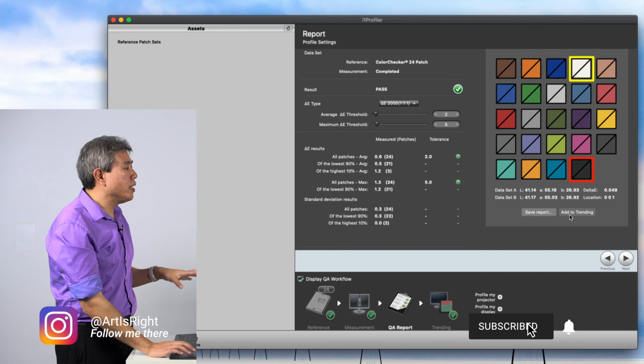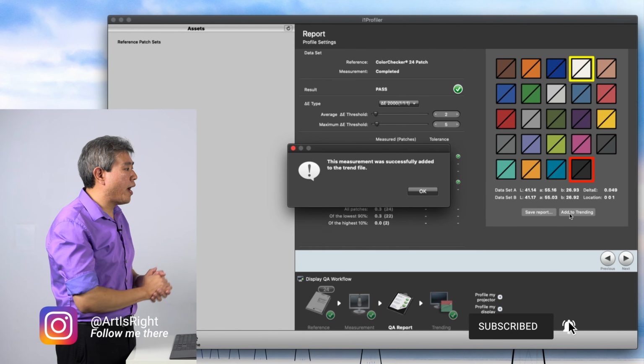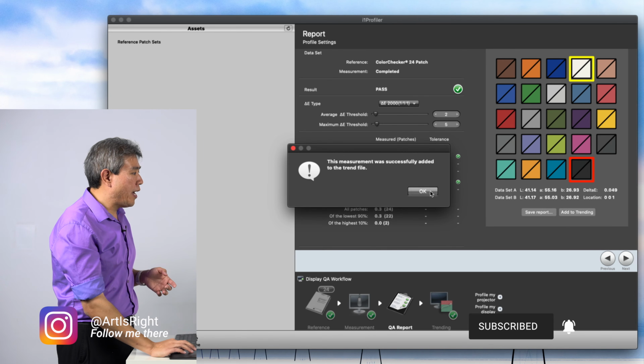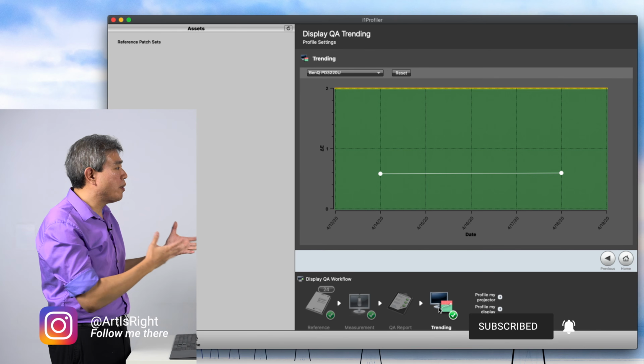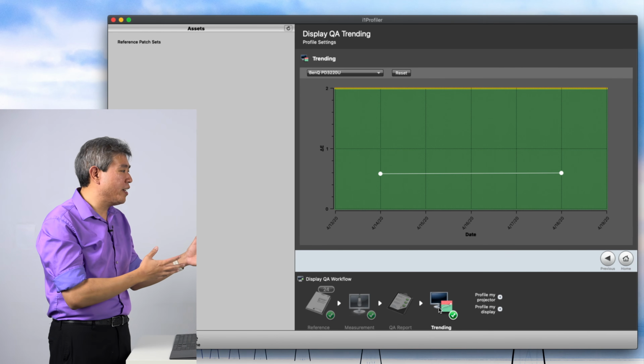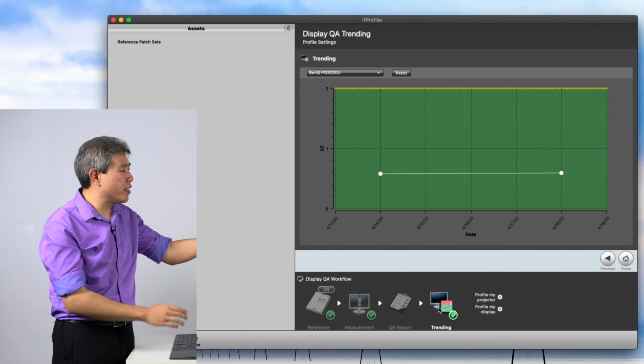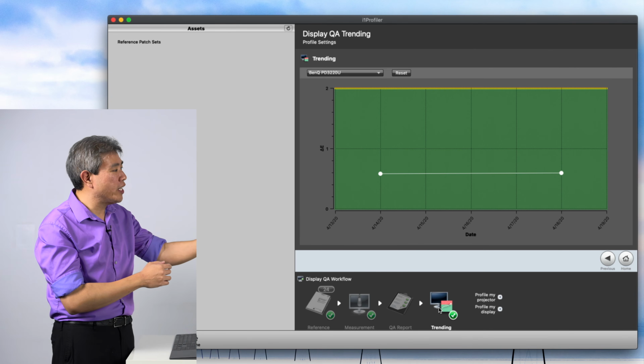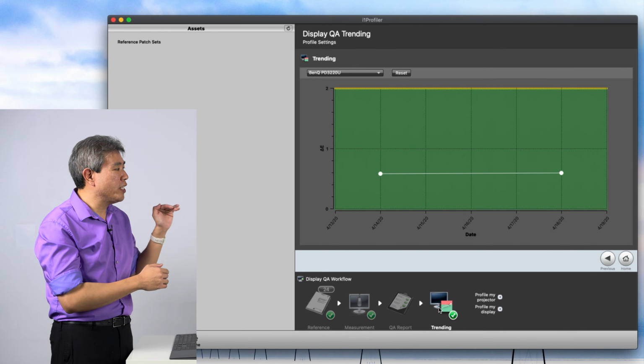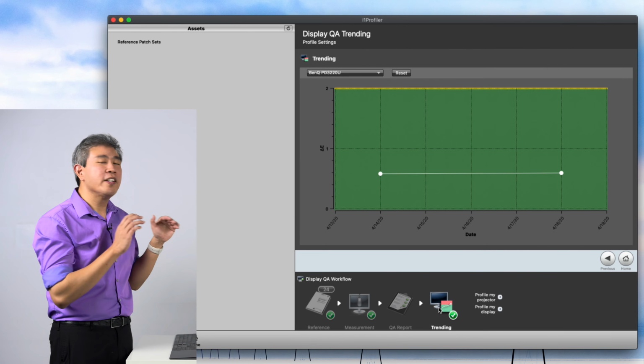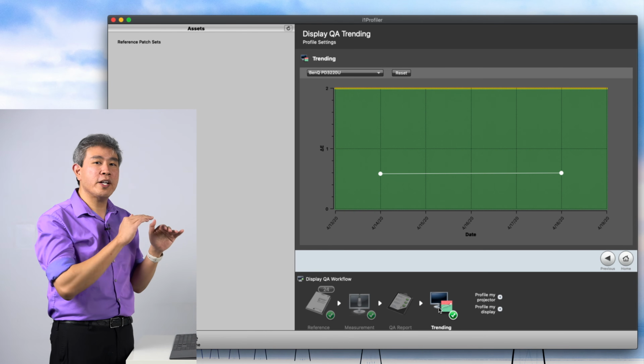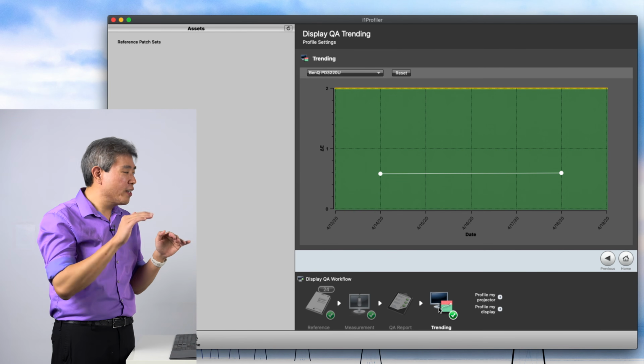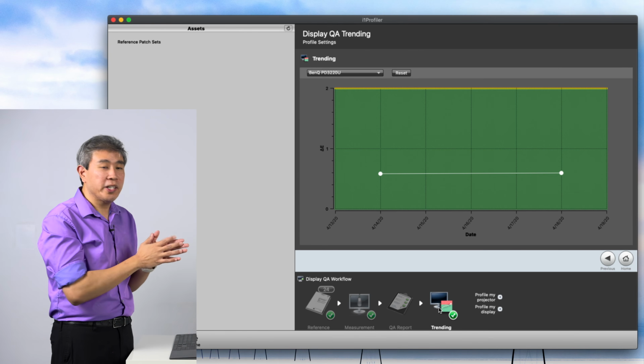Last thing, what you can do here is you can click to add to trending. The nice part about adding things to trending is because i1Profiler allows you to come in here and add different trending points. In fact, what you're seeing right now is already done a calibration test, and this trending is showing the line really straight. You want that in your display. You want it to trend either straight or downwards. And that's going to tell you that you're getting a really great calibration.